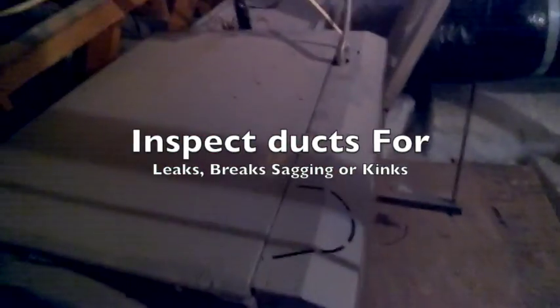So up here doing a checkup on these systems for the summer, and it's our first time being here, so I wanted to check all the duct seals. So what I'm looking for up here is just want to make sure the air quality for these people is good and the duct's solid with no crushes and no kinks. I want to make sure all the silicone seals are like this, solid, which they are, which this is a good builder, so I knew they would be.